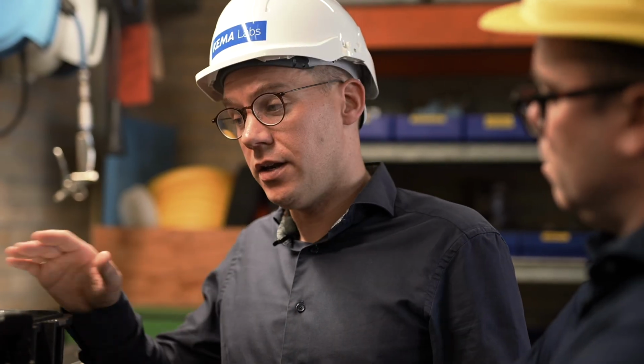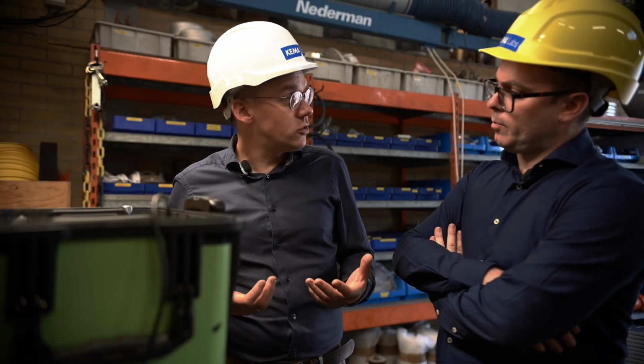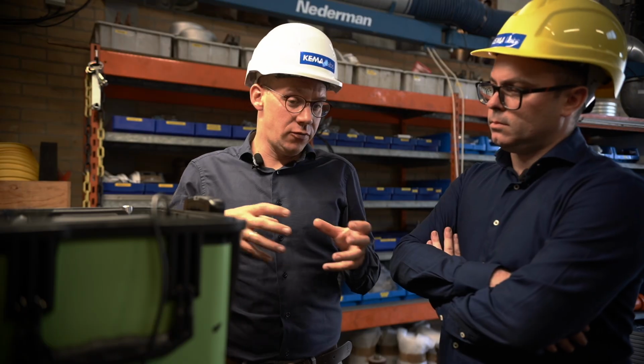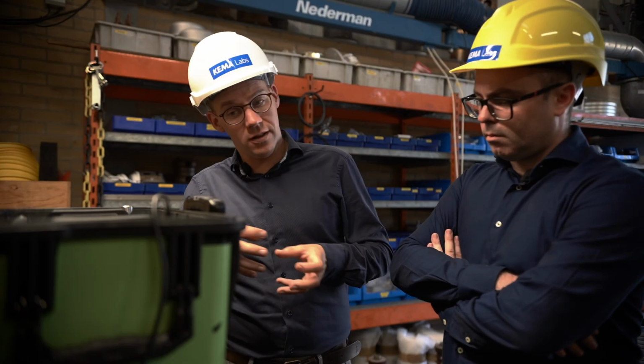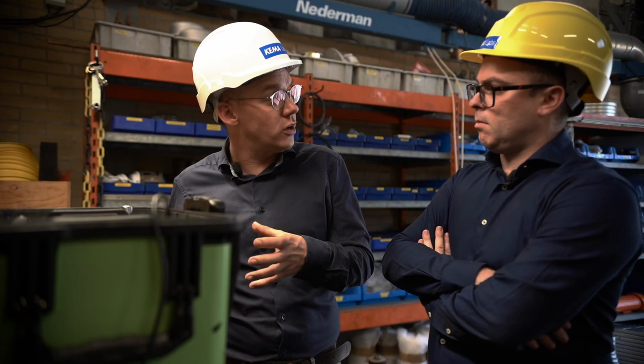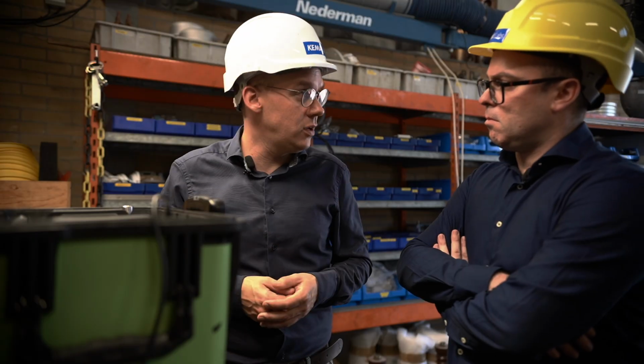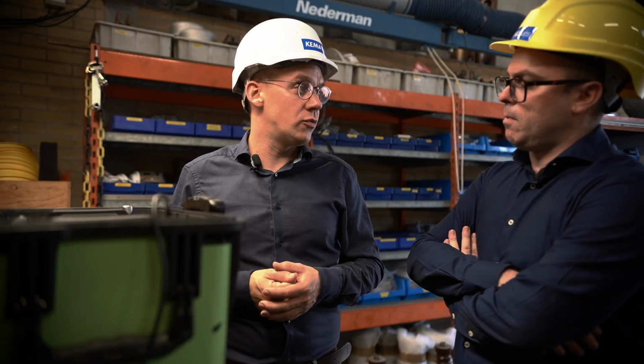One of the things now known is that when alternative gas circuit breakers interrupt current multiple times, the gas degrades, and this analyzer can directly give an indication of the change in the mixture due to the different operations performed. This is good for a customer to know, because they have a footprint of the gas before the test started, and also a footprint after the tests have been completed, which could be good information for them.